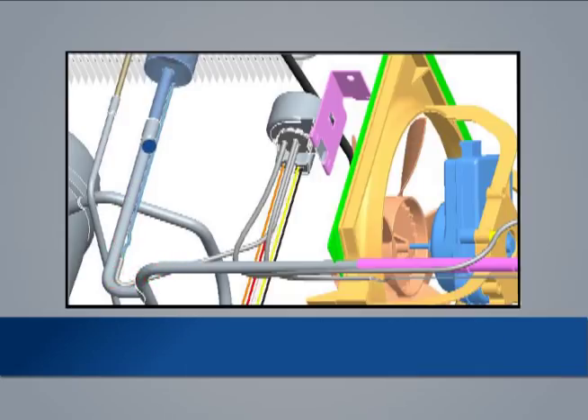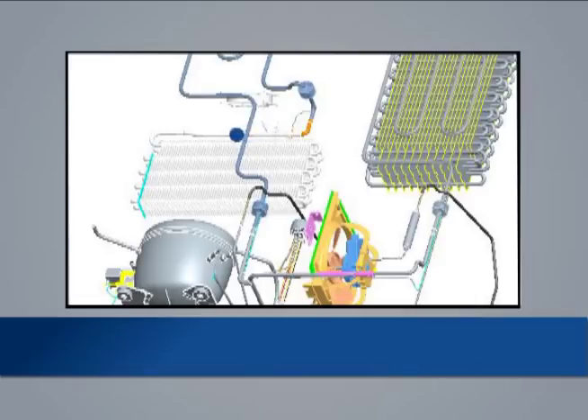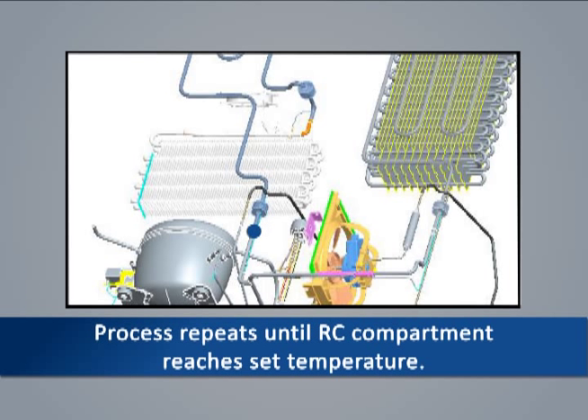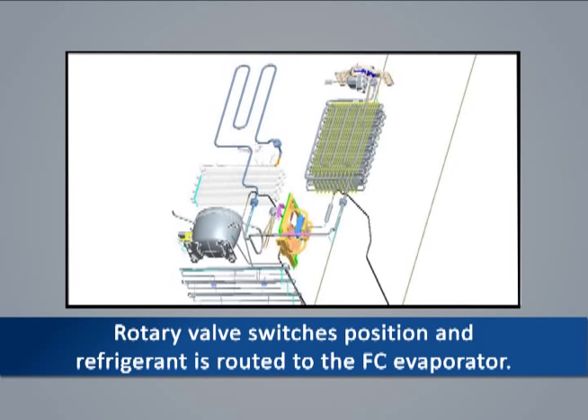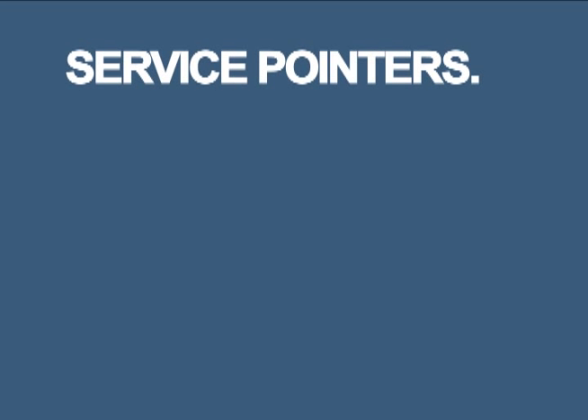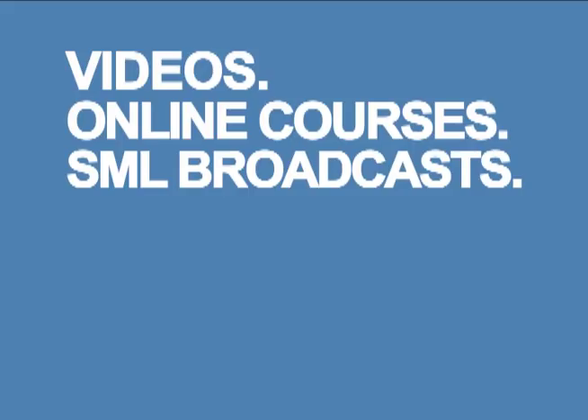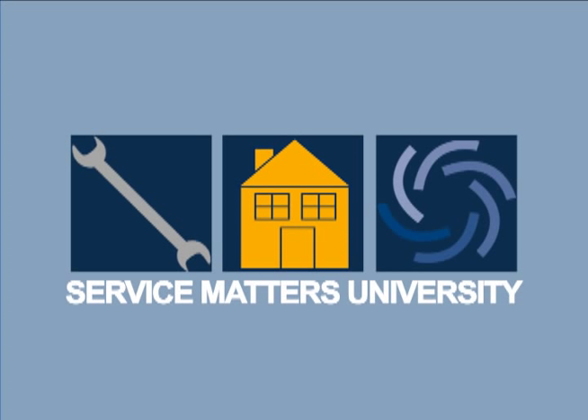When the refrigerant sprays out of the cap tube into the larger evaporator tubing, the high temperature, high pressure liquid transforms to a low temperature, low pressure liquid. As this low temperature, low pressure liquid passes through the evaporator, it absorbs heat and changes state to a low temperature, low pressure vapor. This vapor continues through the suction line back to the compressor, where it is again compressed and the process continues. When the RC compartment reaches the set temperature, the compressor shuts off. When the FC compartment requires cooling, the rotary valve switches position and the refrigerant is routed to the FC cap tube and FC evaporator until the FC set temperature is reached.